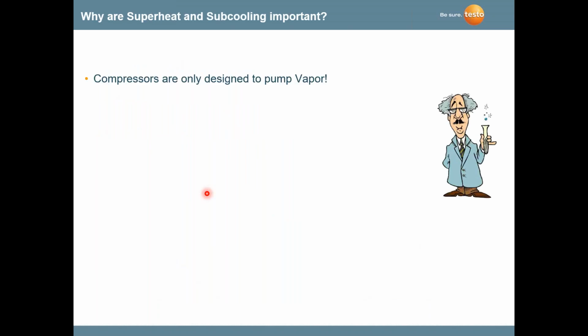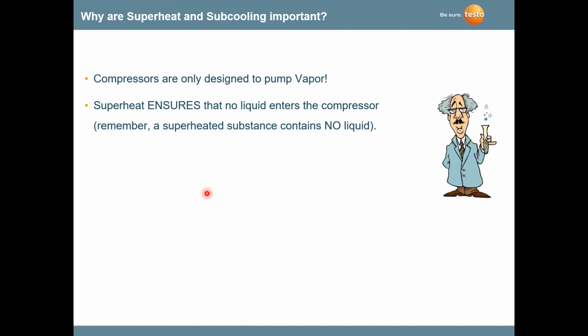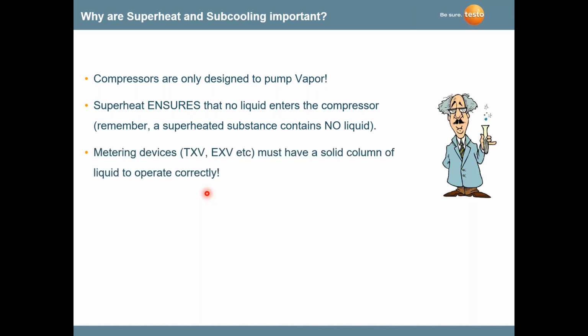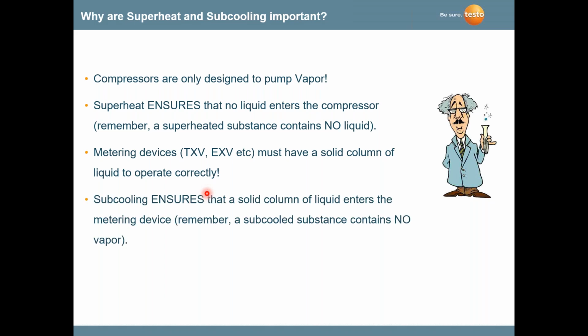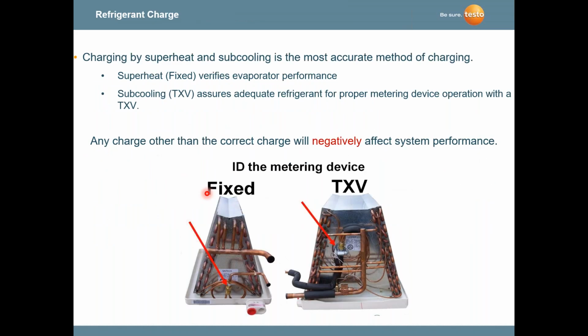So why are we talking about superheat and subcooling so much today? Well, compressors are only designed to pump vapor, and our superheat ensures that no liquid enters the compressor. Our metering devices must have a solid column of liquid to operate correctly, and subcooling ensures that a solid column of liquid enters the metering device.